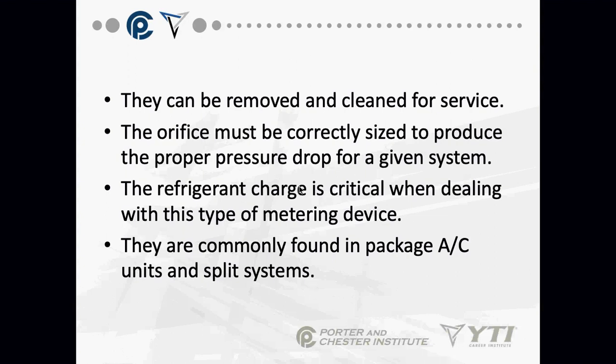So when you have a critically charged system, okay, and you have a leak, or you have a low charge, well, there's a leak someplace, okay? You've got to recover the refrigerant out of the system, put it into a vacuum, and recharge it according to the factory default charge. Where are you going to find the factory default charge? In the manual. Either in the manual or on the nameplate, on the data plate that's on the unit. It says it.